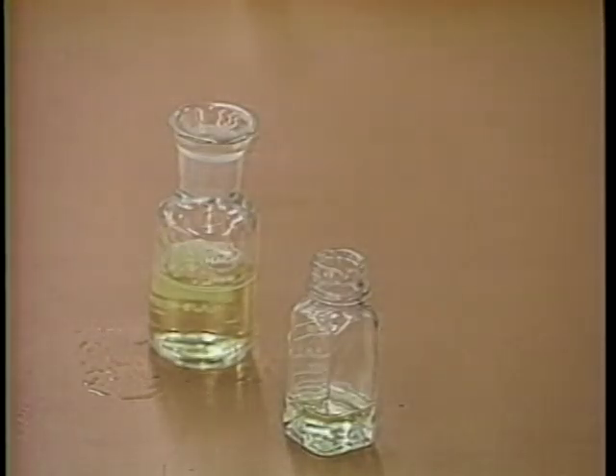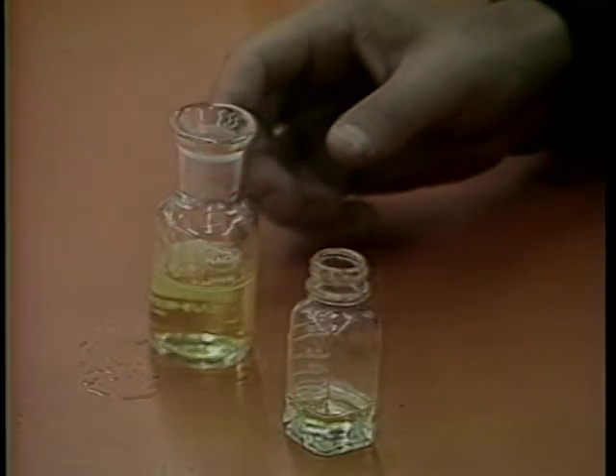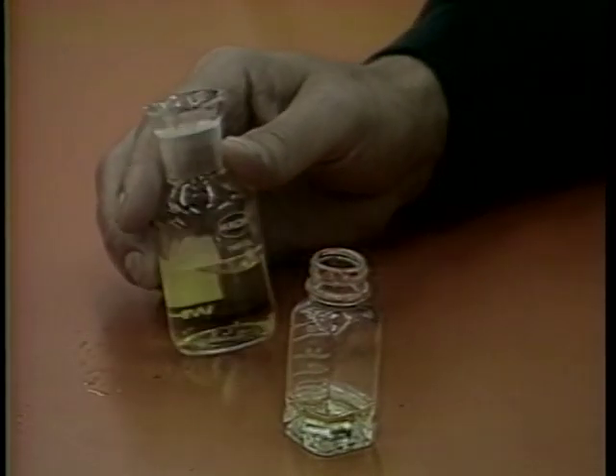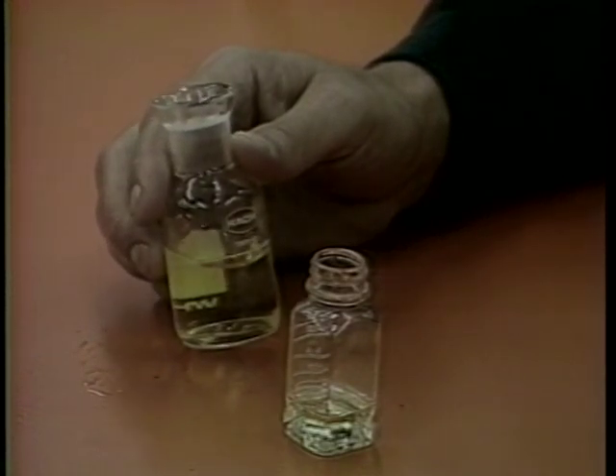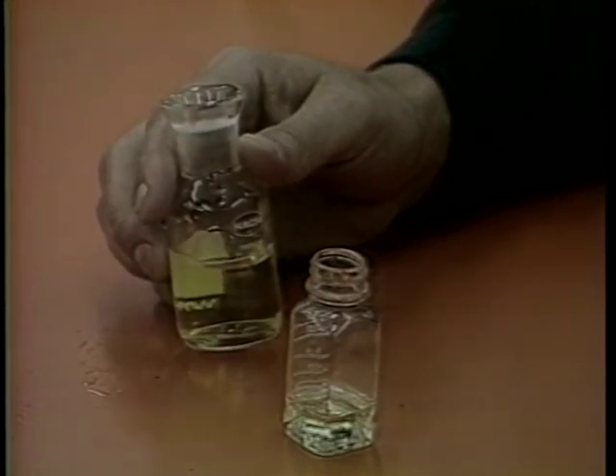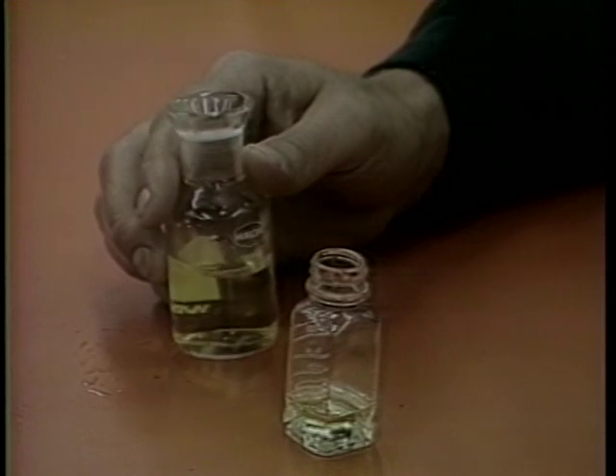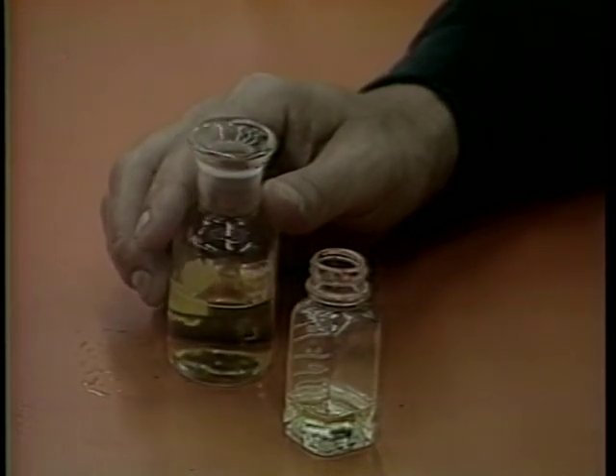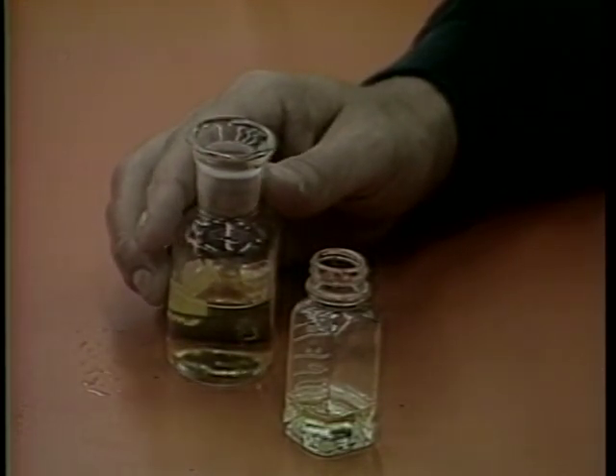If the results obtained in the high range test are below 3 milligrams per liter or parts per million, proceed with the low range test. In the low range test, a larger prepared sample is used, which results in a greater sensitivity at low dissolved oxygen concentrations. To measure the dissolved oxygen using the low range test, proceed as follows.